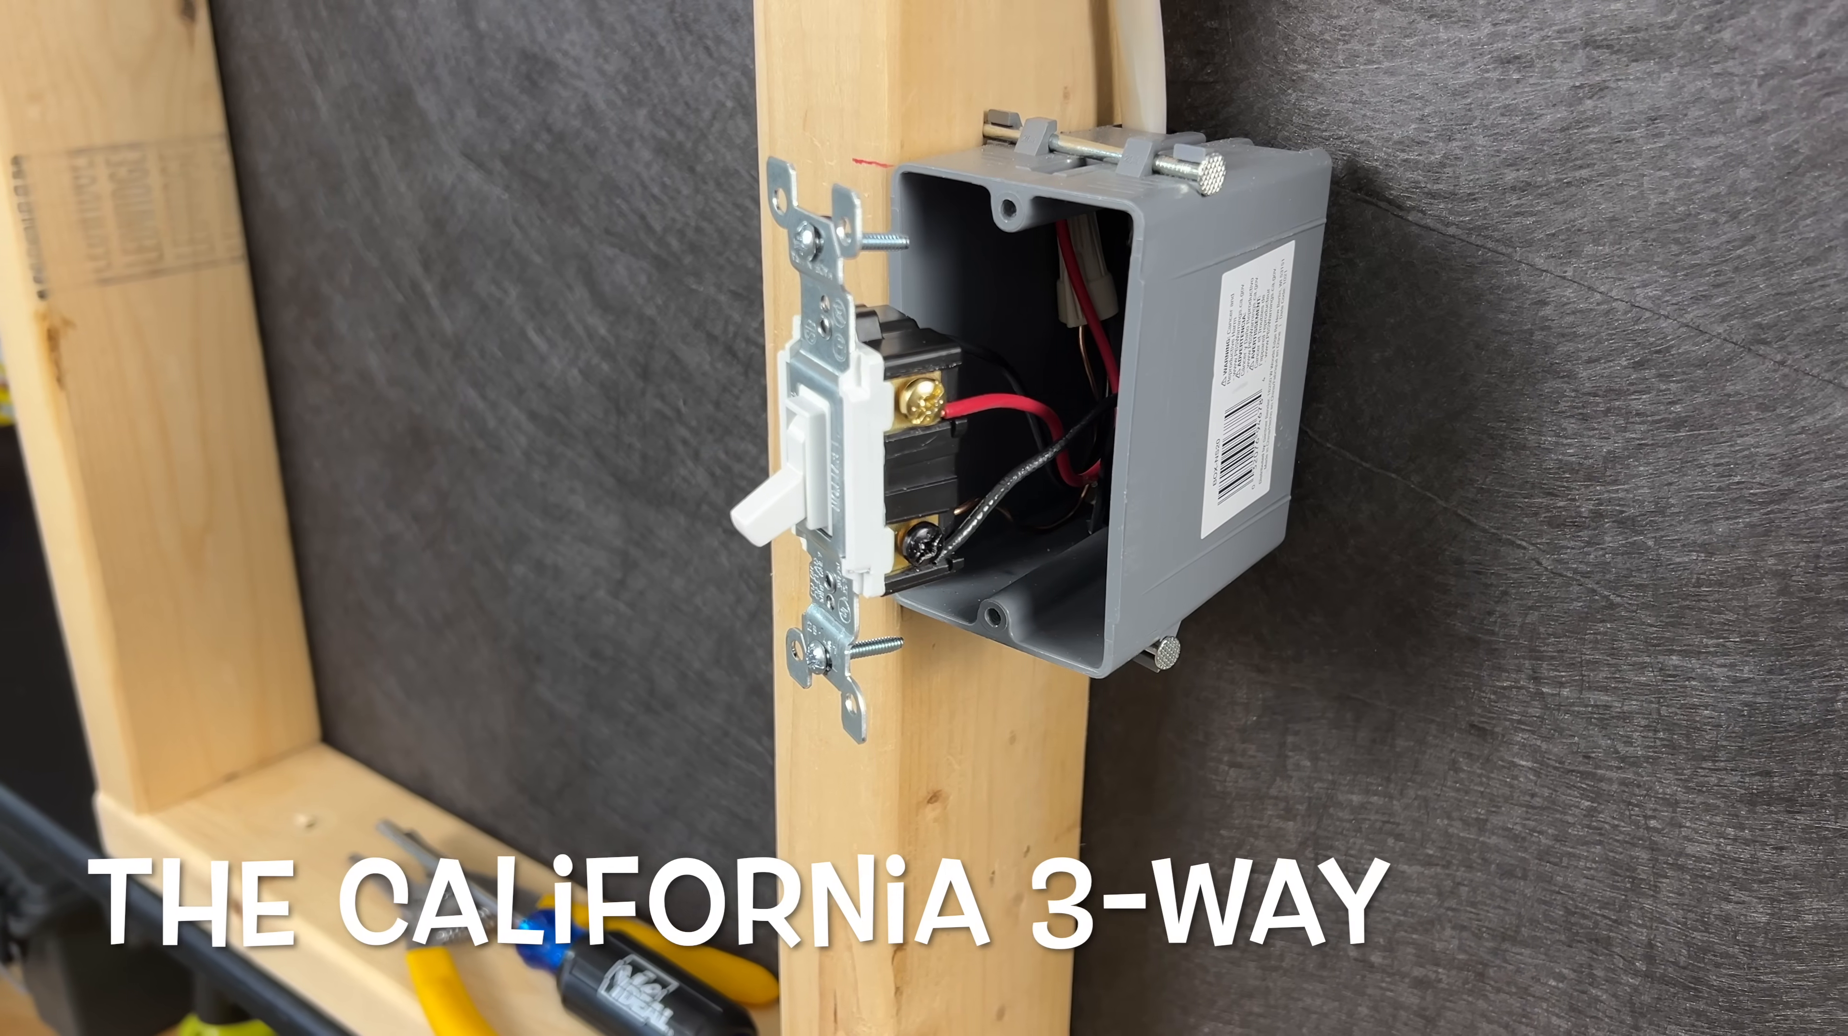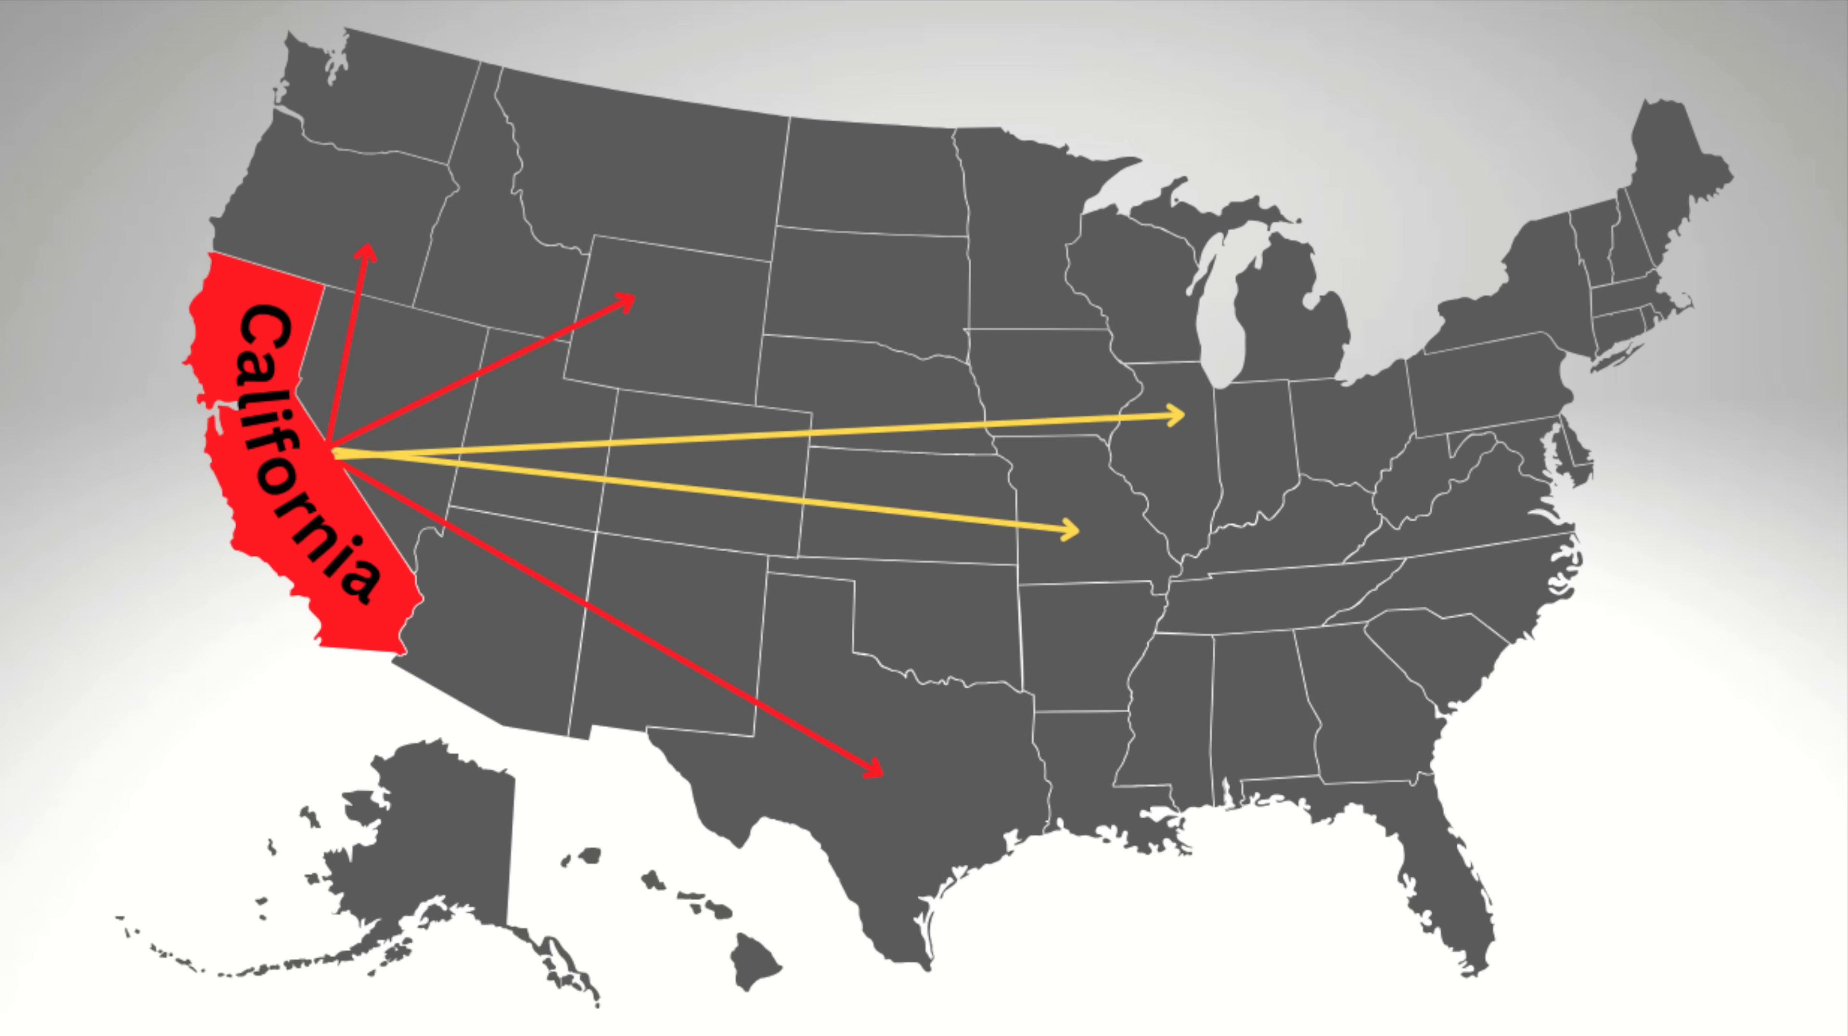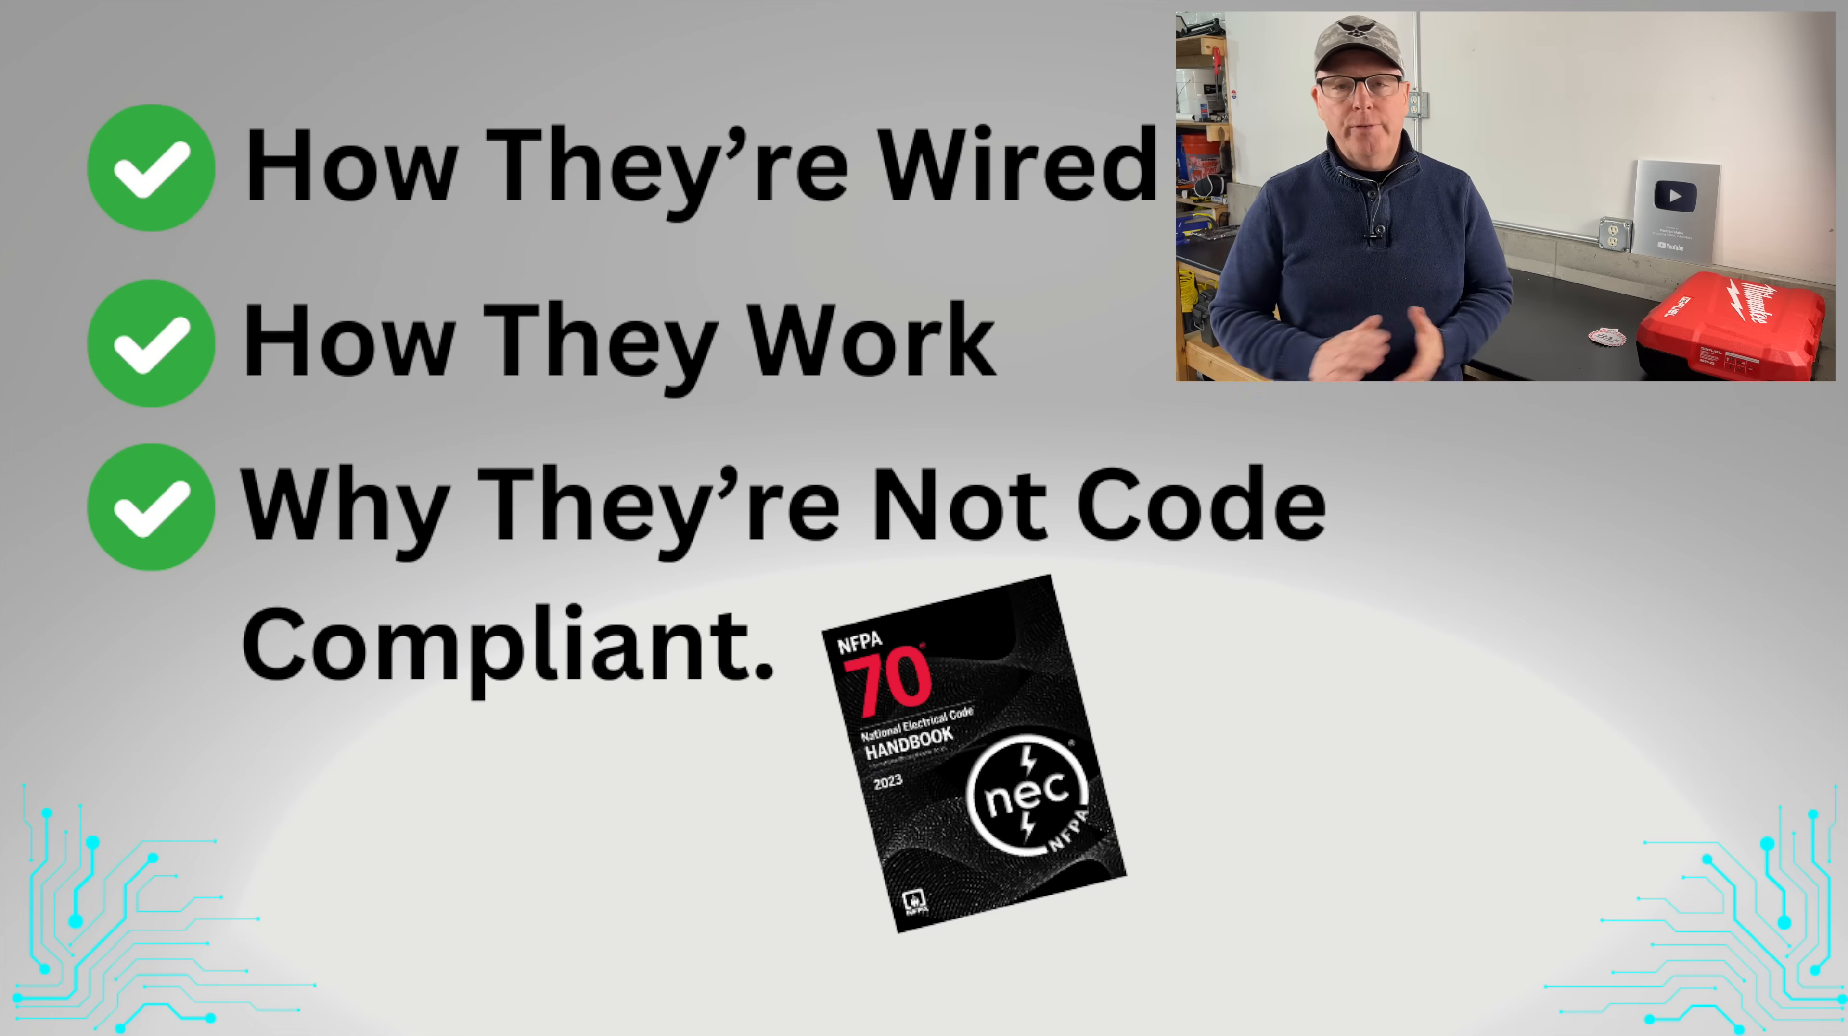The California three-way is a rare and now illegal wiring method not known by many electricians. A few counties in California had requirements where you couldn't run more than three conductors in certain raceways. Over the years, the California method was discovered and used by electricians from other parts of the country. They are out there and can be confusing to wire when replacing switches. In this video, I'll show you how they're wired, how they actually work, and then we'll take a look at the code book and figure out why they're not compliant for use today.